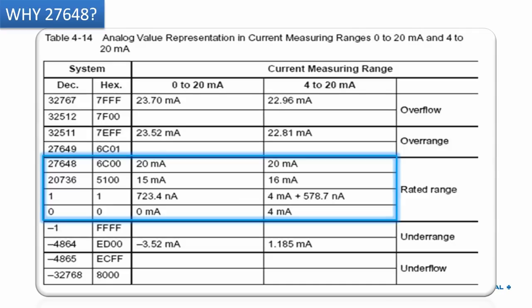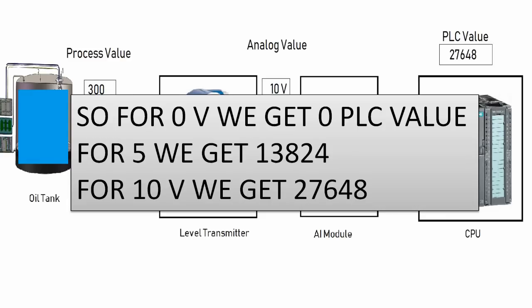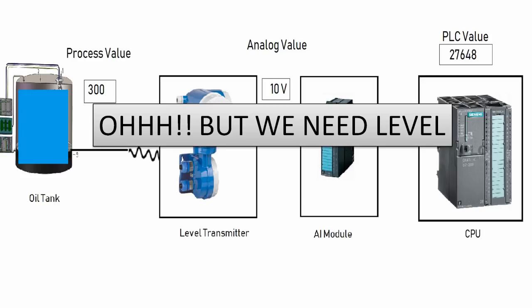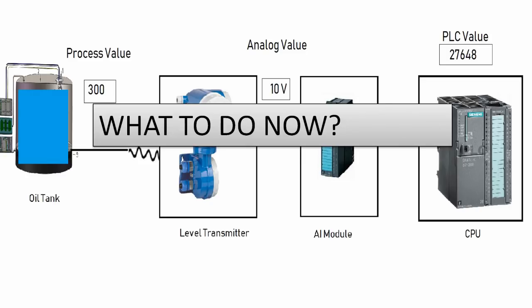For example, if there is a cut in the wire, you will understand it because the value will not come in the rated range. You will analyze that. If the value is exceeding — like a short circuit causing current more than 20 milliampere — that is overflow, and Siemens has reserved spaces to detect that. That's why we take only 85 percent of the total value. But this raw value — 0, 13824, or 27648 — is not the actual engineering value we're looking for, which is 0 to 300.